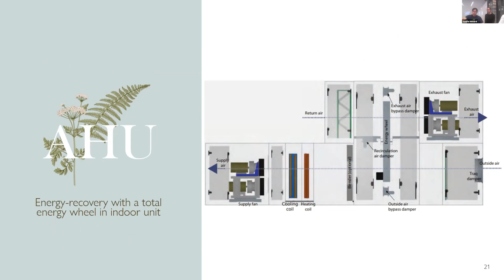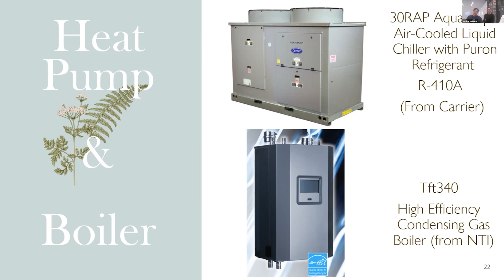So far, the chiller we use is the Aquasnap air-cooled chiller with a 30-ton capacity, which has an EER of 10.4. The fascinating part about this chiller is that we can install it underground, like in the mechanical room in the basement, without a cooling tower because it's air-cooled. And the boiler we use is the TFT 340 high efficiency condensing gas boiler, which is an energy star style gas boiler. It emits 50% less CO2 to the atmosphere, and it can save up to 40% of the heating bill. Moving on to the duct layout.